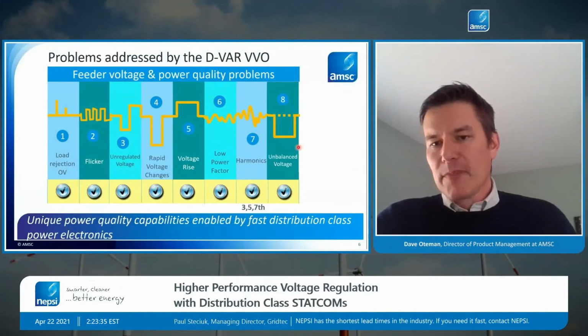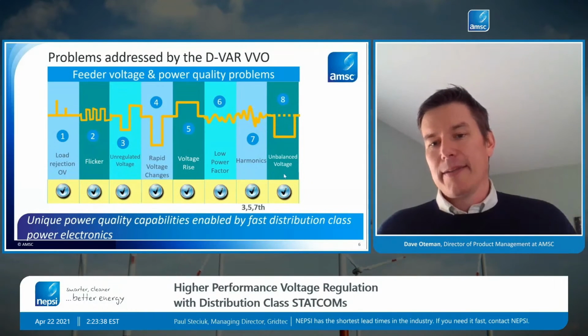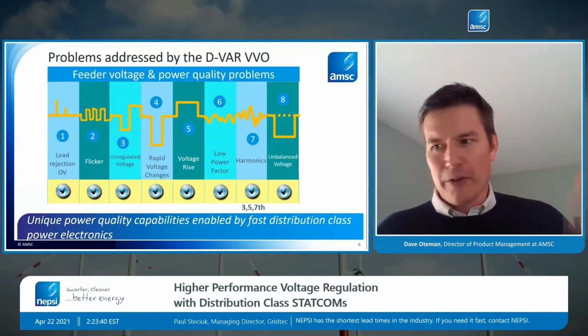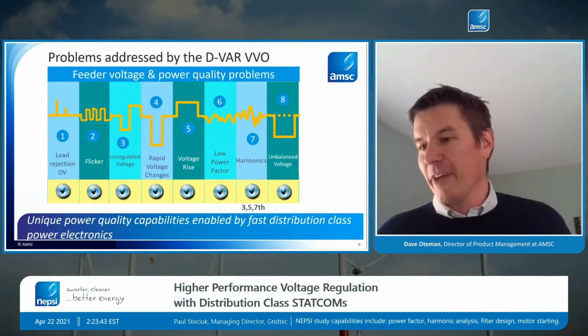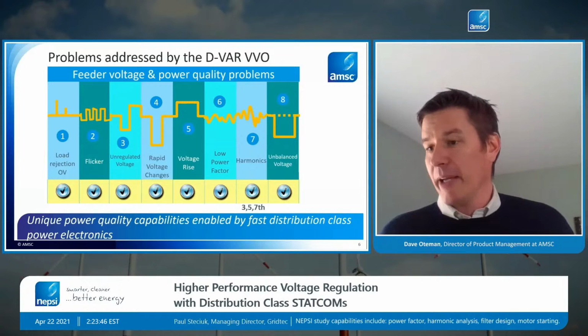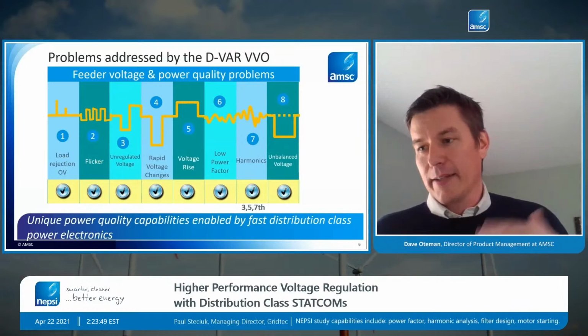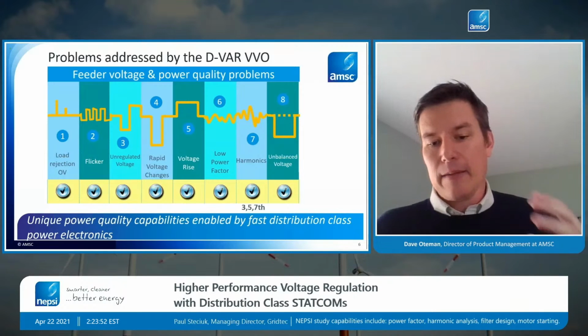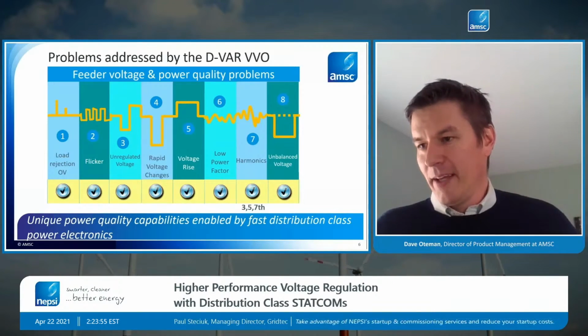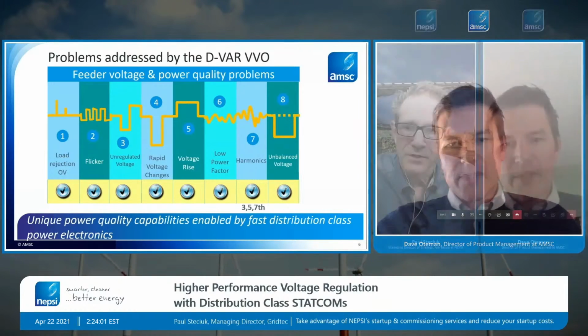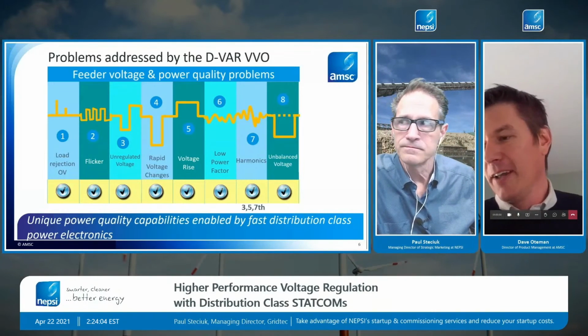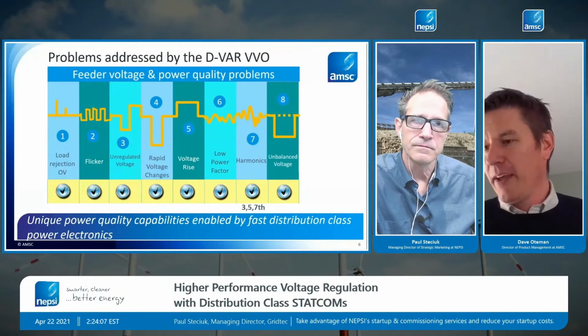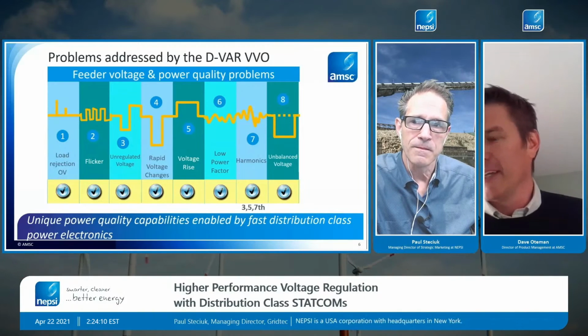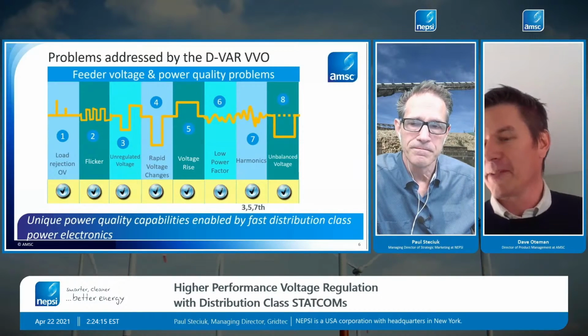So the VVO distribution class STATCOM is able to independently operate all its phases. For example, phase A could be fully inductive, phase B could be fully capacitive, depending on how unbalanced that system is. And a STATCOM is generally a more effective way to compensate for voltage unbalance than either a cap bank or a line regulator. So we see that we can cover what I call the gamut of power quality issues based on this power electronics technology, and really fill that gap that today is not being met well with existing mechanical equipment.